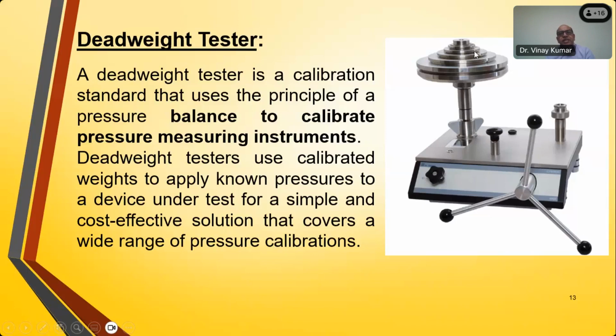When we apply the masses on the piston and generate the pressure with the help of this pump, this balances the masses, and these masses float on the fluid. The masses exert a force mg, and by knowing the area of the piston we can calculate the pressure as mg over A. This is the simple relation, but for accurate measurement there is a complex equation, and we need an accurate measure of the density of the fluid, air, and many other components. But the basic principle is mg over A, force over area.